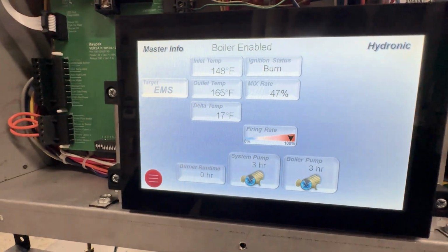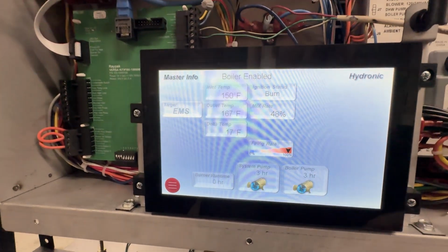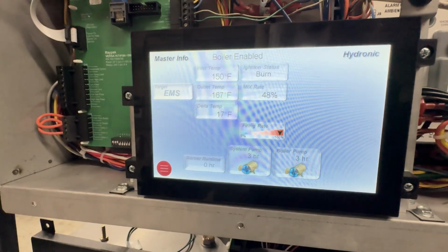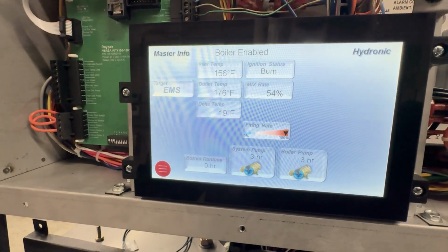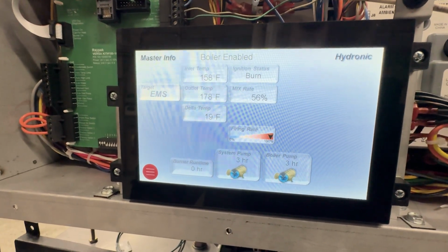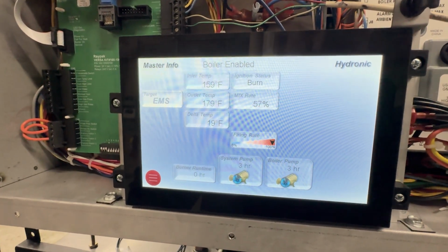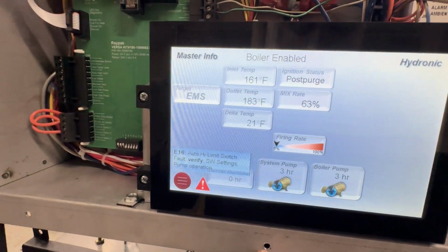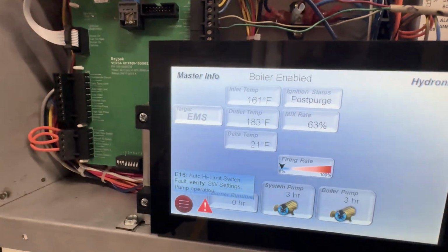Outlet temp's getting close to 170. You'll hear that blower cycle off once that high limit's tripped. 174, 176. We should be tripping, and there it goes. Throw an alarm. Auto high limit switch. So our outlet temp got up to 183.